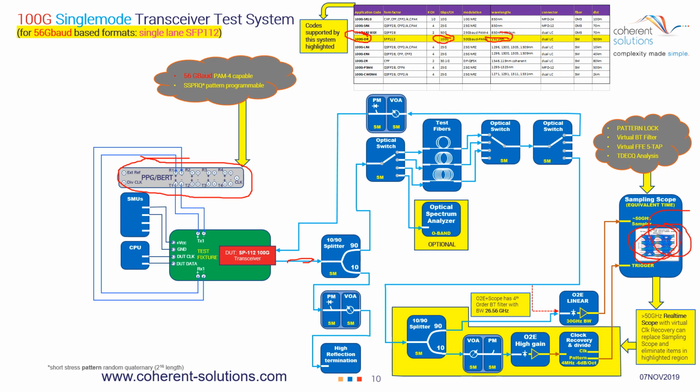Keep in mind that you may need to change these bit error rate testers and pattern generators out, determined by the data rate of the particular transceiver you're trying to test.